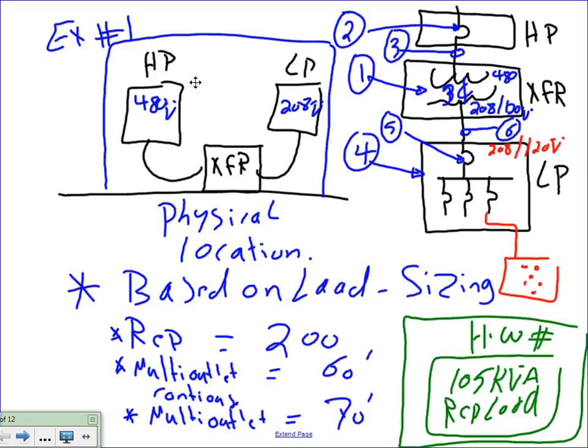Take the following. I have a high voltage overcurrent protection device, feeder, going to a transformer, 480 on one side, 208/120 on the other side, going down to a low voltage 208/120 panel, and I need to size these 5 things. Number 1, the size of the transformer, always 3-phase, always delta 480 on the primary, always Y 208/120 on the secondary, typical. Let me read it one more time: 3-phase, 480 to 208/120 transformer. We need to size it.